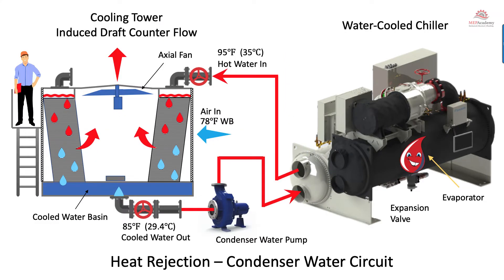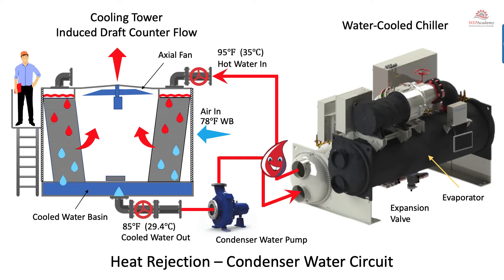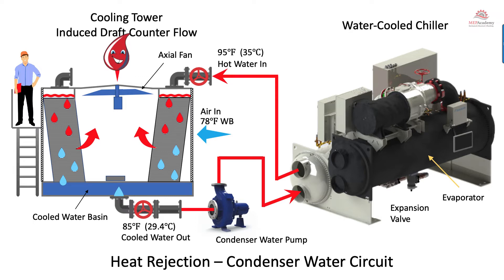The heat arrives via the chilled water — picked up from the room and brought to the chiller. That heat causes the liquid refrigerant on the low side in the evaporator to evaporate, absorbing the heat. It's then taken through the compressor and compressed to a high-side vapor, which passes to the condenser, into the condenser water, and out to the cooling tower — that's how heat is rejected from the building, traveling from the chilled water circuit through the refrigerant circuit in the chiller to the condenser water circuit and out of the building.